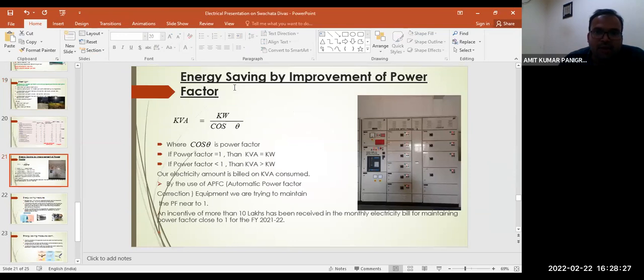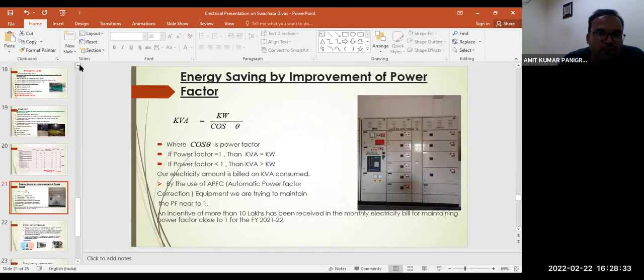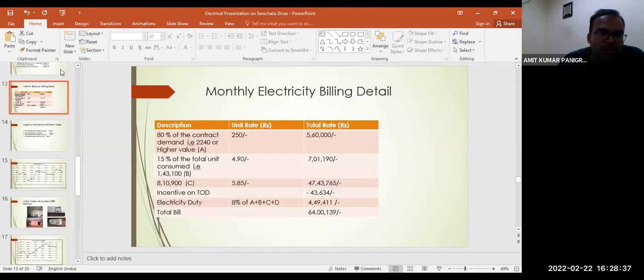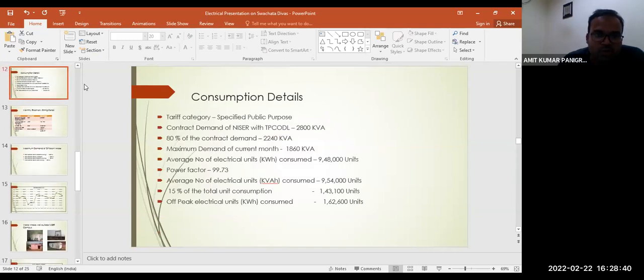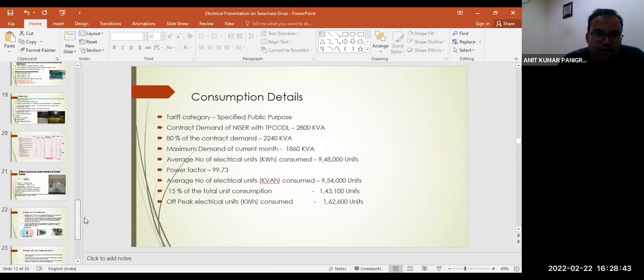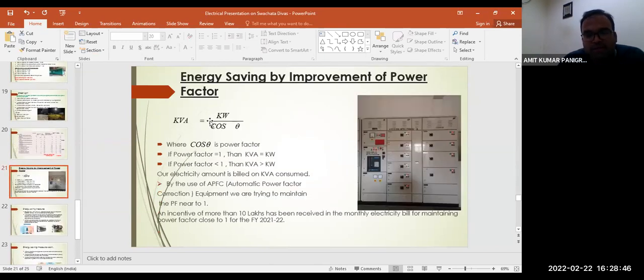One main thing, in the previous slide on energy billing, we saw the power factor. What is the importance of this power factor, we will know here. kVA means kilovolt ampere, and power is a multiplication of voltage and current. So V times A, divided by 10 to the power 3, is kVA, which equals kilowatt divided by cos theta. Similarly, kilowatt is V times I times cos theta, and this cos theta is the power factor.